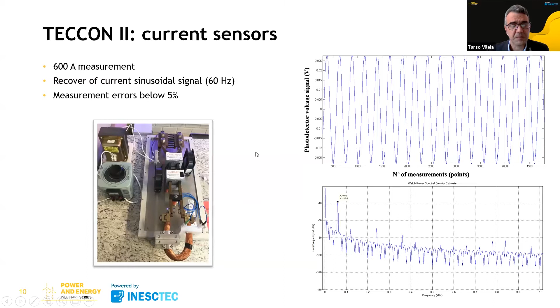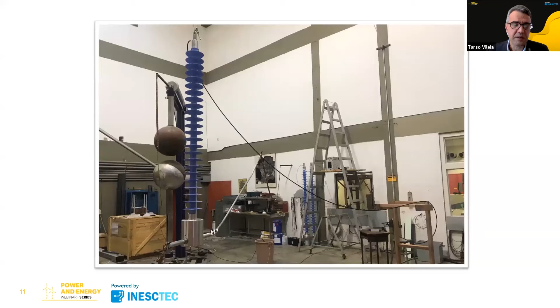Next, please. Here we have set up on a high voltage lab. We were testing the whole system connected together. The electronics were here in this box, and the insulator is here, as you can see, the blue one. The electronics are inside this box on a ladder beside the insulator. The test here was to check if the electronics were able to keep running during an impulsive current test, and it was okay. It has passed. It's 5 or 6 meters of distance here. We had more than 60 kiloamps in the impulse.